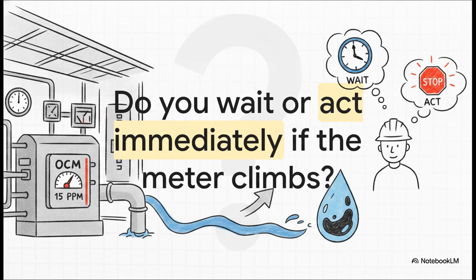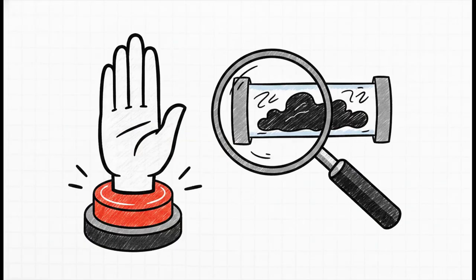All right, I want you to put yourself in the shoes of the chief engineer for a moment. You're down in the engine room overseeing a routine bilge discharge, and you notice your inline oil content meter's reading is steadily climbing up toward that 15 ppm limit. Do you wait a minute to see if it maybe stabilizes and drops back down, or do you act immediately? You act immediately. You must instantly stop that discharge and investigate.